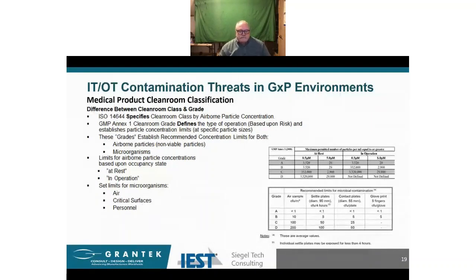And just to be clear, it's impossible to have a Class A cleanroom or a Class B cleanroom or a Class C cleanroom, because we're mixing terms there, right? We can have a grade A, grade B, grade C, or grade D, or we may have an ISO Class 5 or an ISO Class 7 cleanroom. And the knowledge and understanding and the use of those terms is extremely important for us in these environments that we're talking about. Next slide, please.